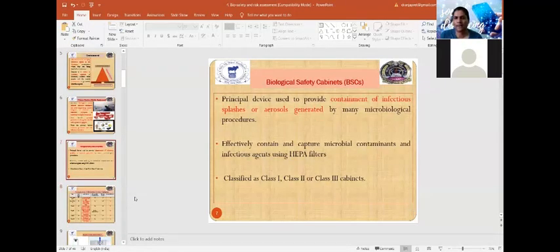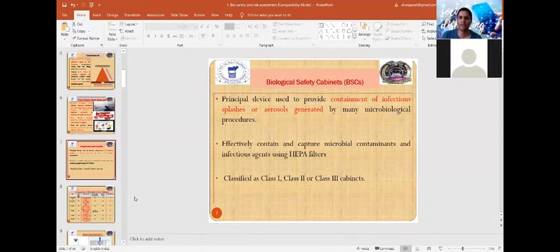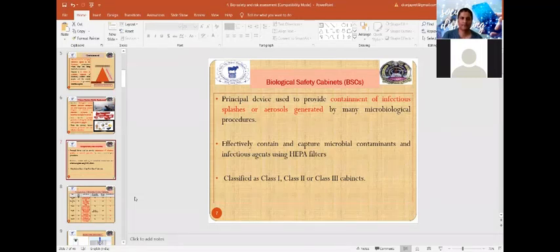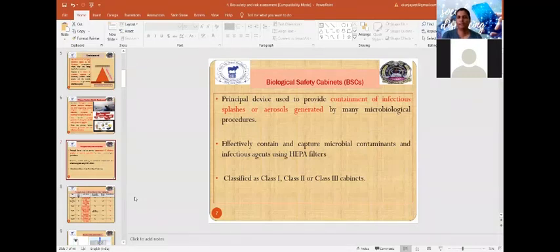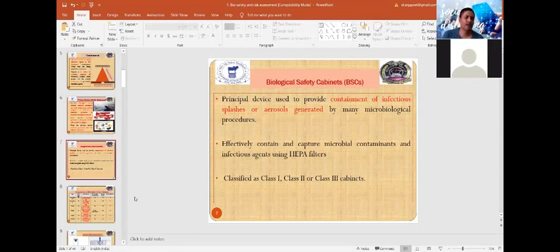Biological safety cabinets are a primary barrier and serve as the principal device providing containment of infectious organisms, either from splashing or aerosol generation, during microbiological procedures such as pipetting or inoculations. For effective capture of microbial contamination, biosafety cabinets are fitted with HEPA filters.